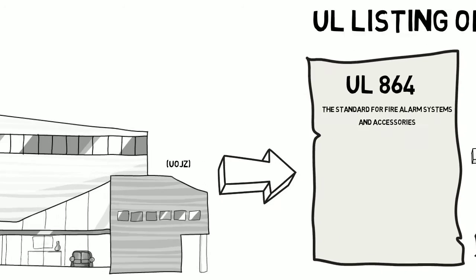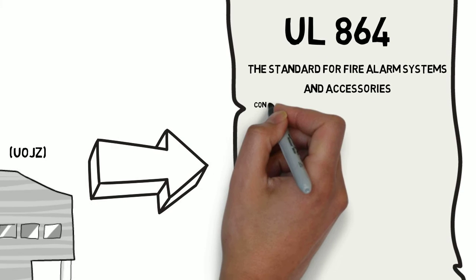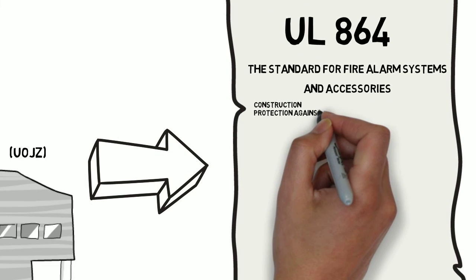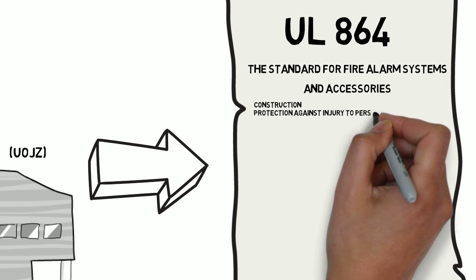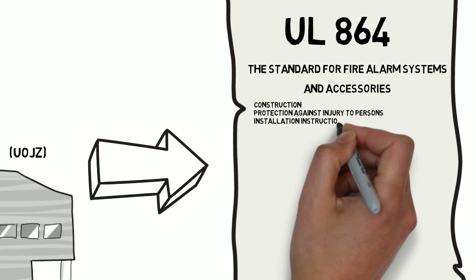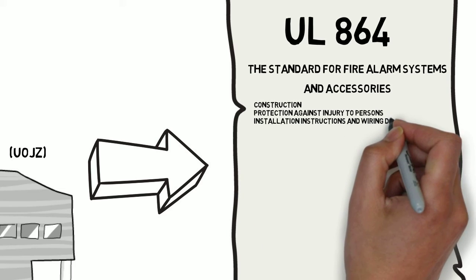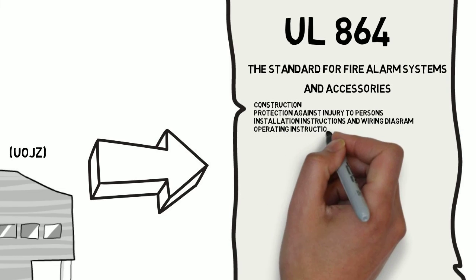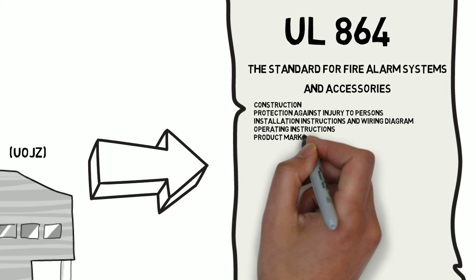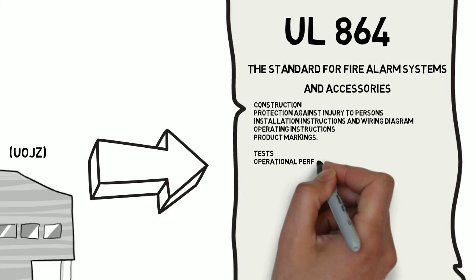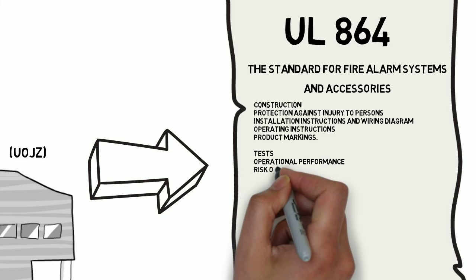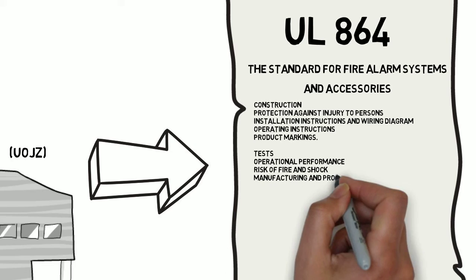UL 864 is used to evaluate the equipment. It has requirements under construction, protection against injury to persons, installation instructions and wiring diagram, operating instructions and product markings. The tests cover operational performance, risk of fire and shock, manufacturing and production line testing.